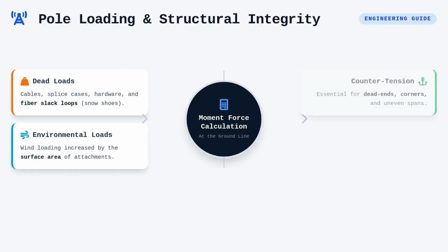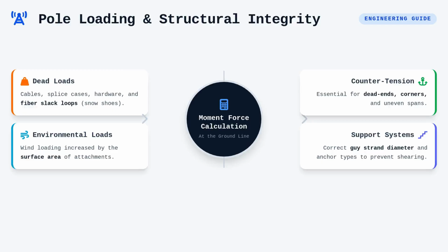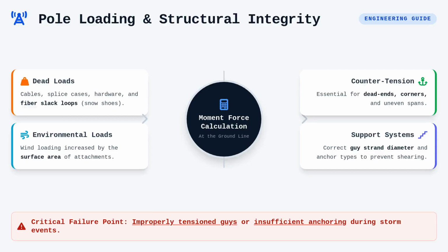The use of guy wires and anchors is essential to counteract the tension forces at dead ends, corners, or uneven spans. These structural support systems must be designed to direct the resulting forces safely into the earth, preventing the utility pole from leaning or shearing under stress. Improperly tensioned guys or insufficient anchoring are primary failure points in storm-stressed aerial plants, so the selection of the correct guy strand diameter and anchor type is a critical engineering task.